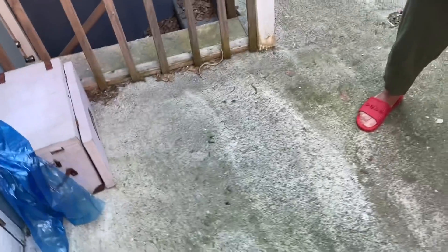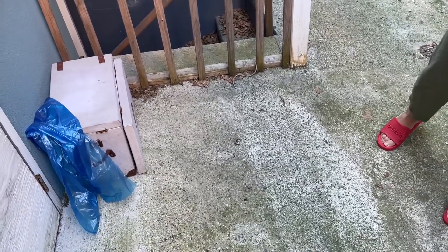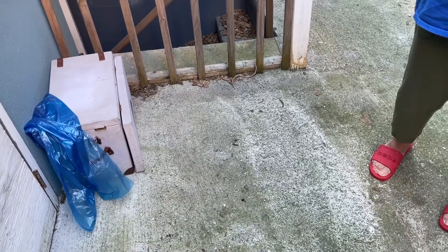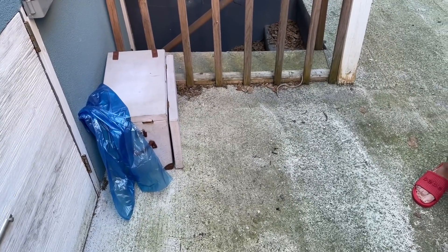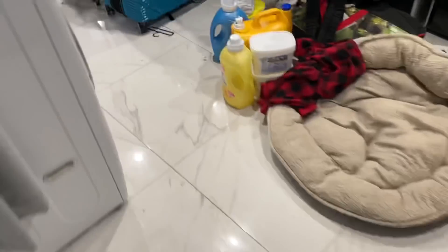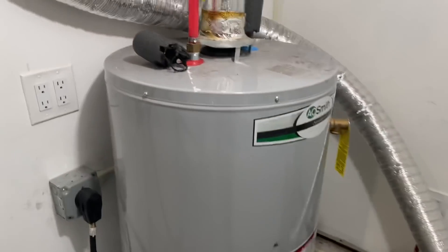Let's talk about the second guy who quoted $2,700 to replace the water heater. Was he giving you a power vented water heater? He said 'Rheem.' The only solution here is either a power vented water heater — what that means is it utilizes a PVC pipe on top and directly exhausts outside — or we address this properly. I have to turn off the water heater because it's a hazard condition.